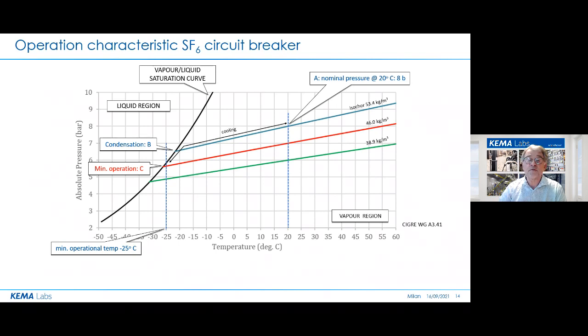The second loss process is through leakage and permeation, as you can see here. Well, this happens, of course, during the entire life of a breaker and can reach the minimum functional pressure for insulation. And this is the condition D, which is the condition of a type test. Well, in this design here, the blue track is the operational lifetime cycle of this breaking device.